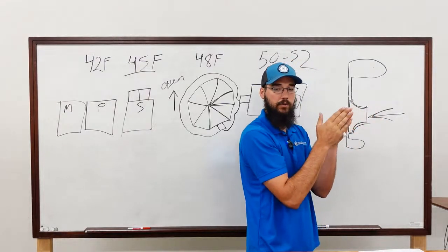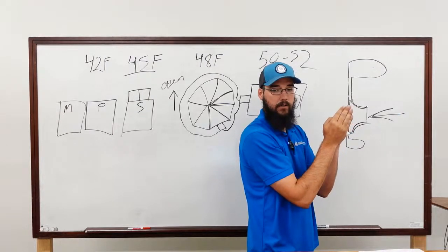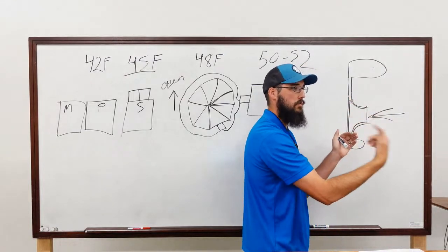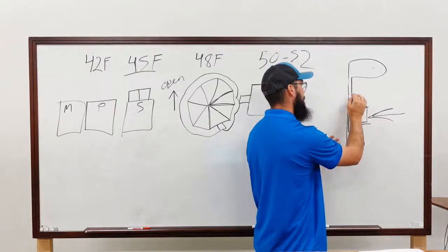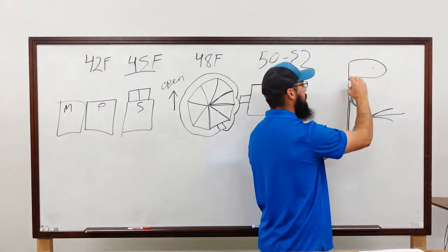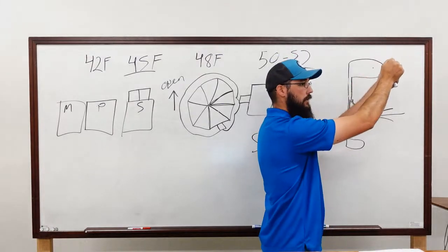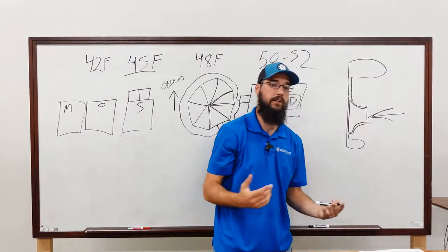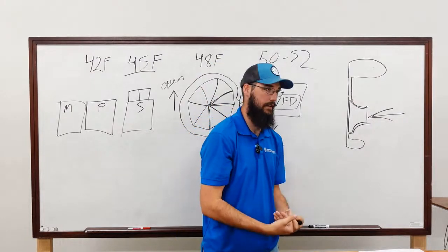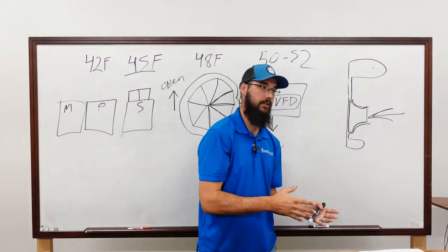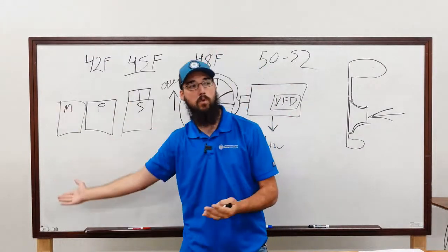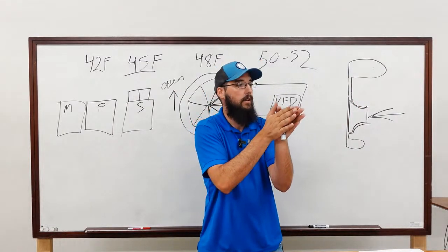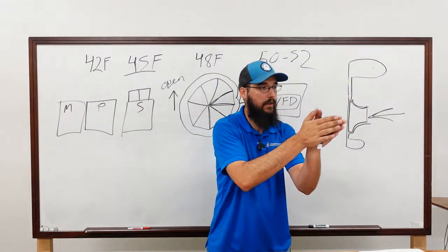And the molecules then begin to compress against each other. And as we're just constantly throwing more and more molecules into that, by molecules, I mean refrigerant, eventually it all compresses and it builds pressure as it gets literally pushed out into the volute. And by the time it reaches the volute assembly, which then spins down into the condenser, pressure has been created, and it's been converted from a centrifugal force, being thrown and channeled into this tiny little channel, where it then gets compressed and then out into the volute.